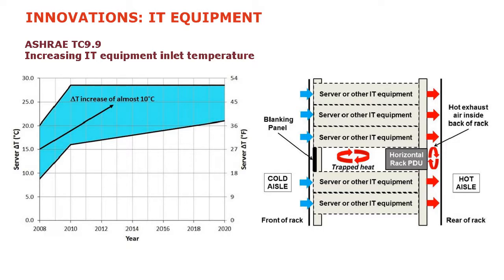The idea being that if we can elevate that temperature, the hotter we can supply air to the server and maintain it in a happy state, the less energy we're going to be consuming on mechanical cooling. With that said, we are increasingly trying to move away from mechanical cooling, as both Dave and Billy suggested earlier, so going more towards evaporative techniques or just using ambient cold air.